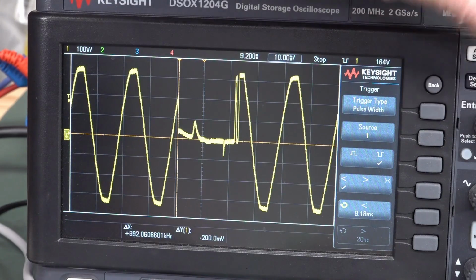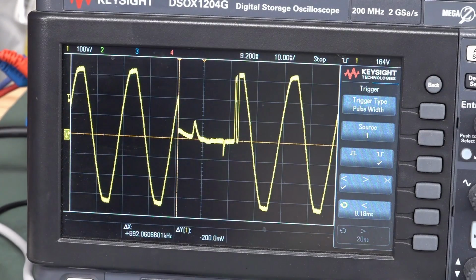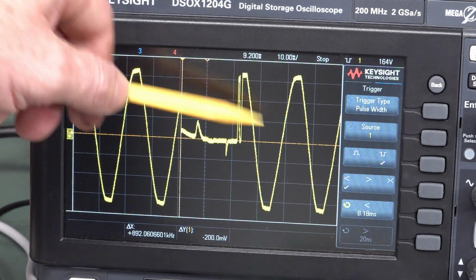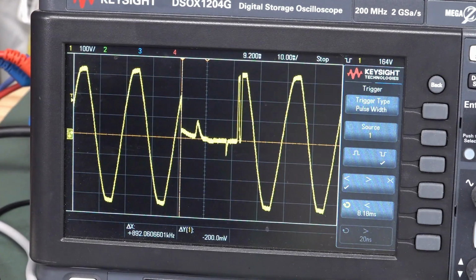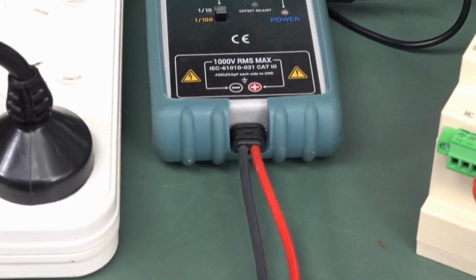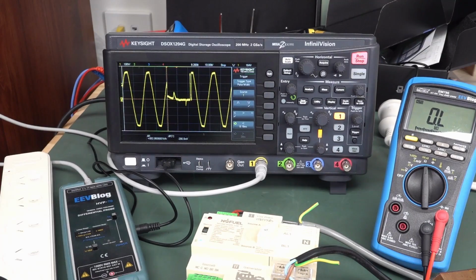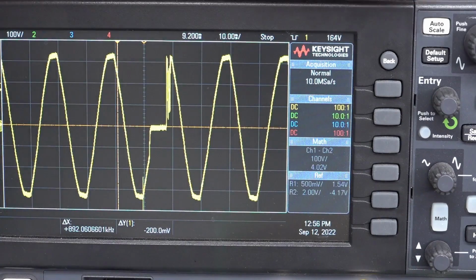As I said, this is not an electronic switch, just a physical thumping mechanical switch. So it has actually switched from one source to the other, even though it looks like the same source, because literally it is, since we've plugged it into the same mains board here. But if you had different source voltages, different source frequencies, and they were asynchronous, you would see it change.